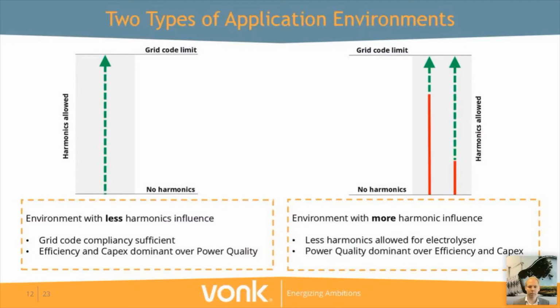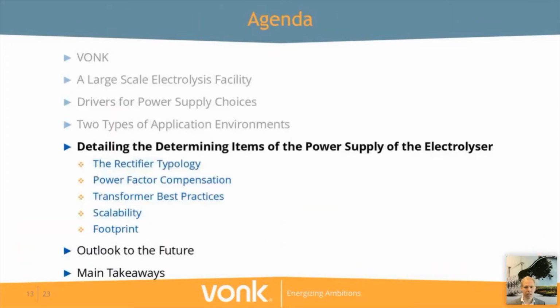Looking at the different application environments, you see that in an environment with less harmonic influence, the power quality becomes a minimum requirement, and you will focus on efficiency and capex over power quality. Whereas in an environment with more harmonic influence, power quality becomes dominant in the mixture over efficiency and capex, and this will come back in different choices that you have to make when optimizing your power supply. We will now go into depth and look at items of the power supply that determine the overall choices and the optimization.